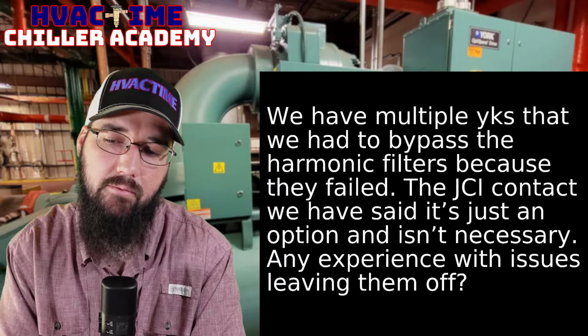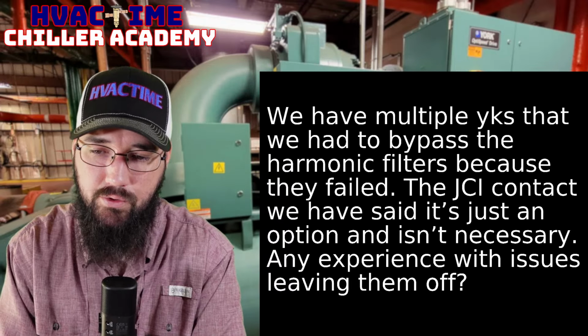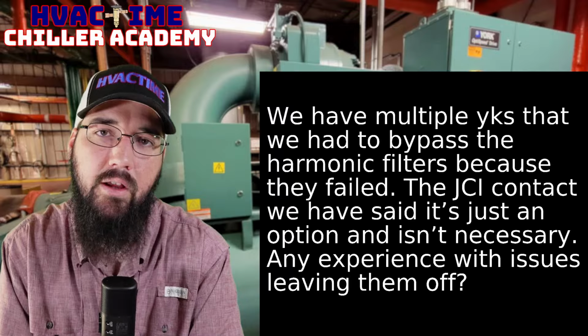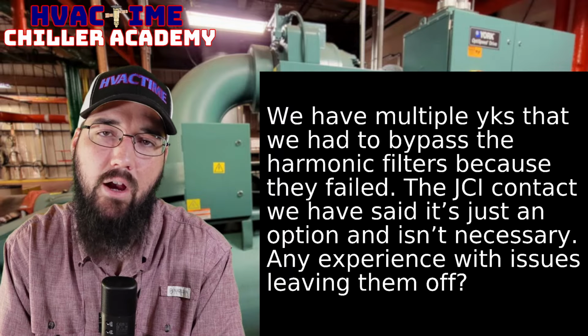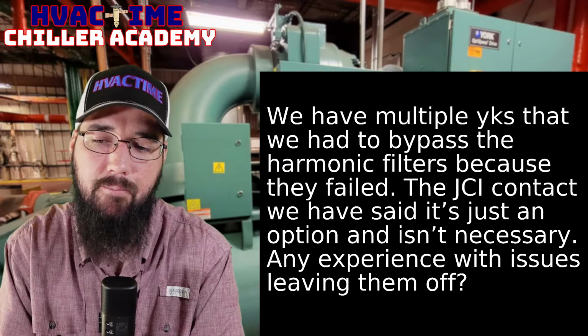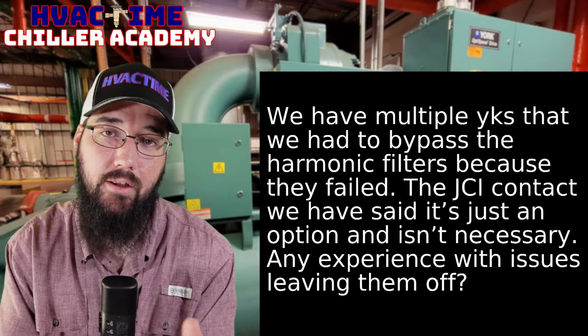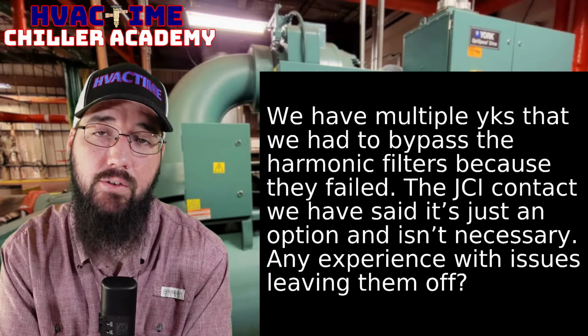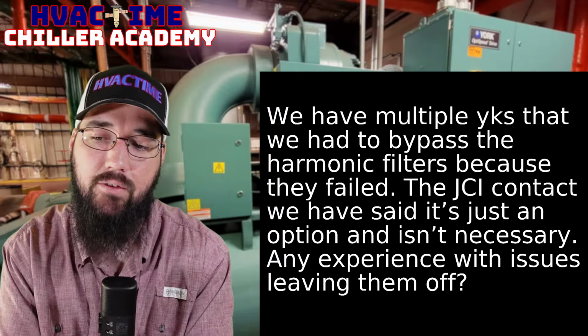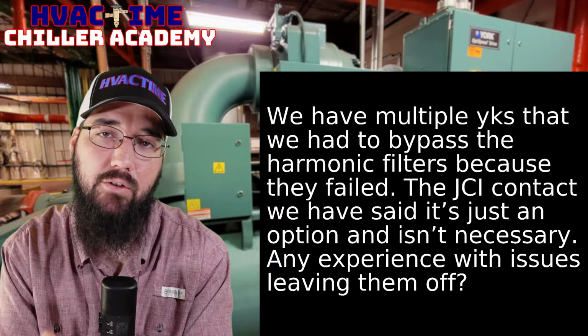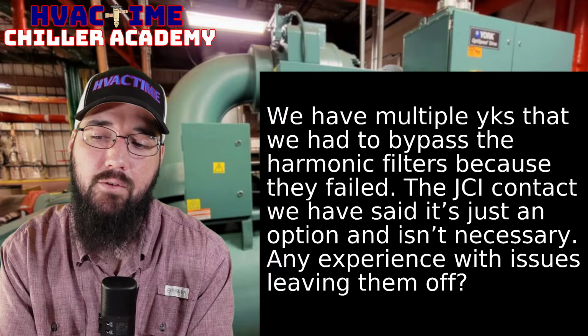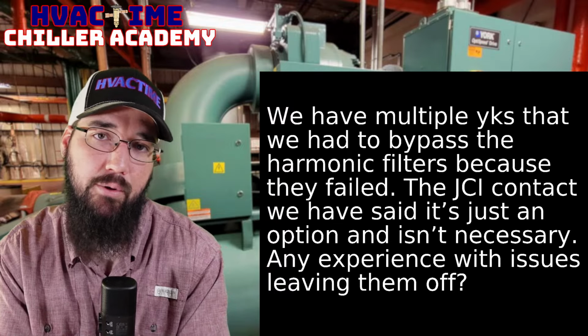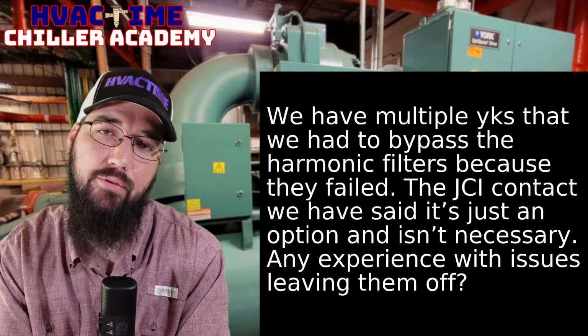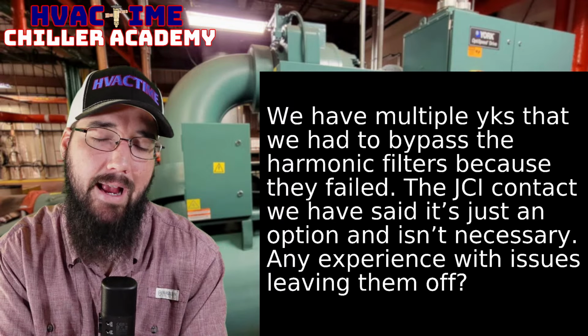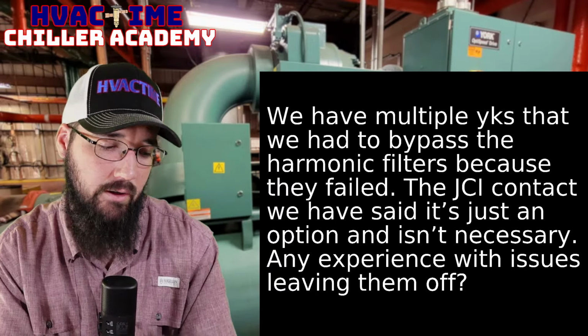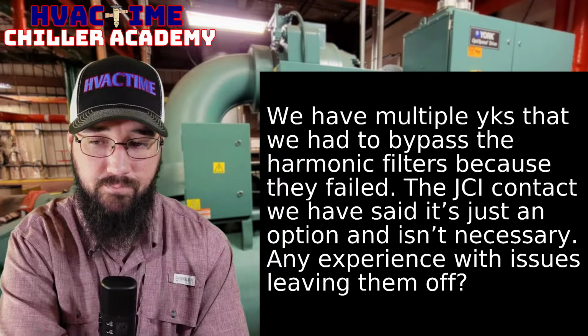But what you saw there is a symptom of when we have too much of that backfeed static feeding into a grid, and they start interacting with other machines. These are the kinds of things that can start to happen. This is why those filters aren't just filtering input power, they're also having to filter the backfeed coming back out of our drive assemblies. We have to be very, very careful with this.